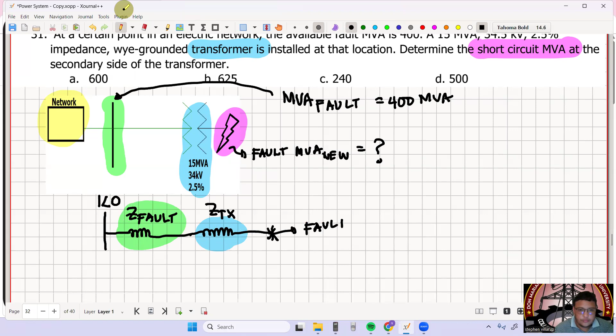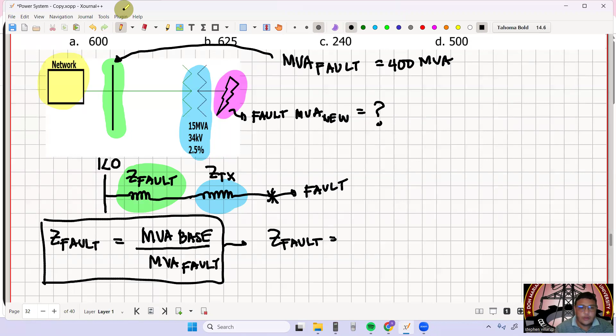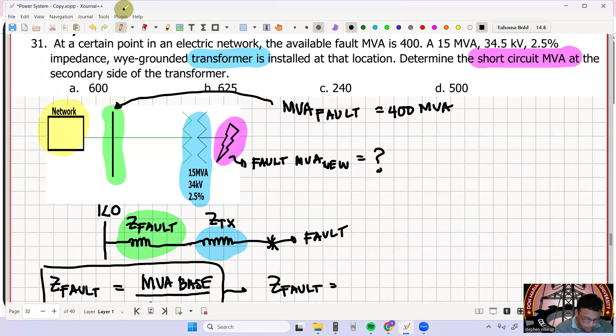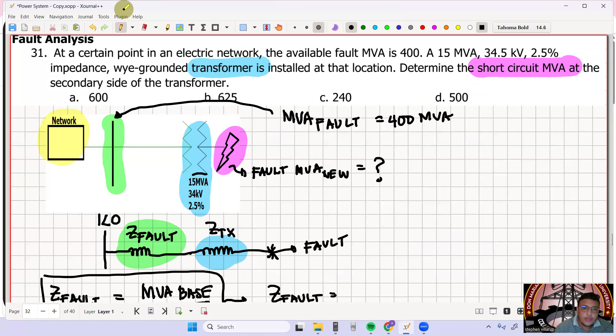So paano natin makukuha yung Z fault? From your fault MVA. So your Z fault now is equal to MVA base over MVA fault. Okay so yan yung ating Z fault. Kung given yung ating short circuit fault, yung fault available, therefore yung Z fault natin is equal to MVA base dito. Take note that is your transformer, ito yung magiging base natin. So this is now 15 MVA over your MVA fault that is 400 MVA.